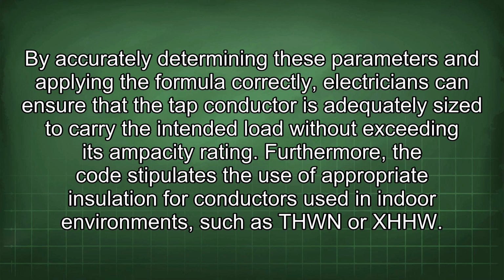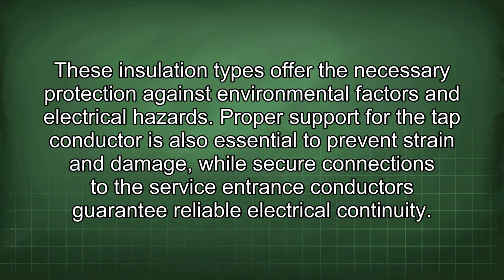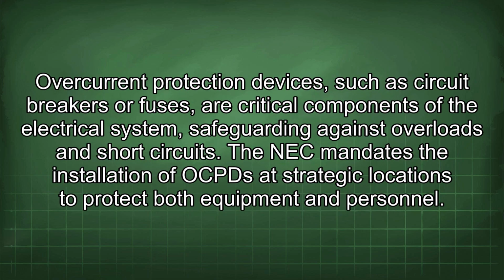Furthermore, the code stipulates the use of appropriate insulation for conductors used in indoor environments such as THWN or XHHW. These insulation types offer the necessary protection against environmental factors and electrical hazards. Proper support for the tap conductor is also essential to prevent strain and damage, while secure connections to the service entrance conductors guarantee reliable electrical continuity. Overcurrent protection devices, such as circuit breakers or fuses, are critical components of the electrical system, safeguarding against overloads and short circuits. The NEC mandates the installation of OCPDs at strategic locations to protect both equipment and personnel.